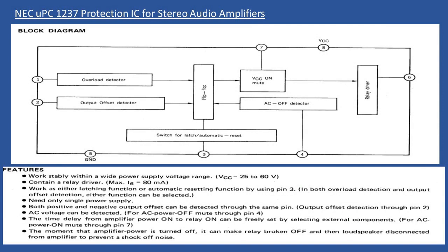Now what's the issue that can happen? Well, it's not uncommon over time, because you rely on a capacitor to form part of that timing circuit, that capacitor starts to dry out and it's no longer able to operate as a capacitor, hold a charge, and you could find that either A, the capacitor, because the value has dropped, charges up very, very quickly, so maybe the timing circuit sort of switches on almost instantaneously, or the switching circuit doesn't operate at all because the capacitor is no longer a capacitor, so there's no charging. So in this case the FET cannot switch on and then energize the protection relay.